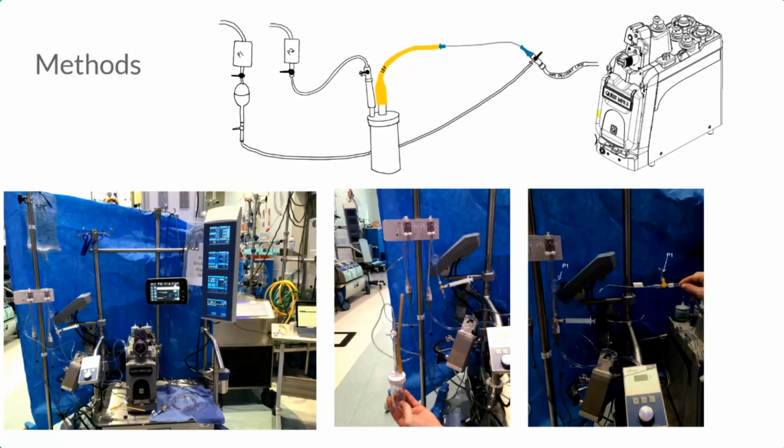So what's actually being measured by P2 is the air displacement. We have the Quest MPS, the fluid will flow down that whole train, end up in our sputum trap, and as it fills, it displaces air, and the air displacement is what's being measured by P2. The reason we had to do it that way, as opposed to a direct measurement, is simply to keep the system closed. Otherwise, we'd have to open it, and that would open up a whole host of things that we can't directly control or measure for.